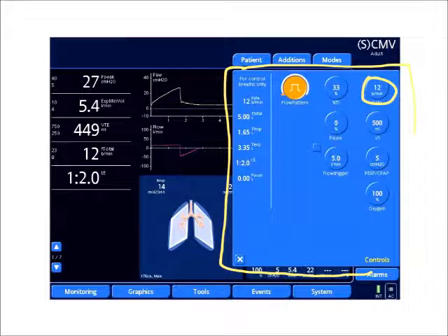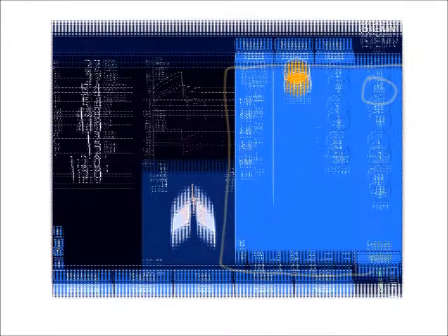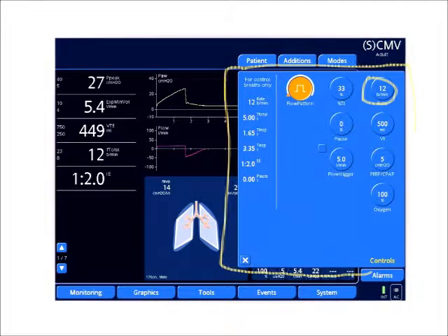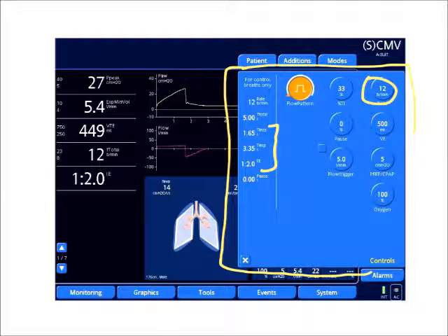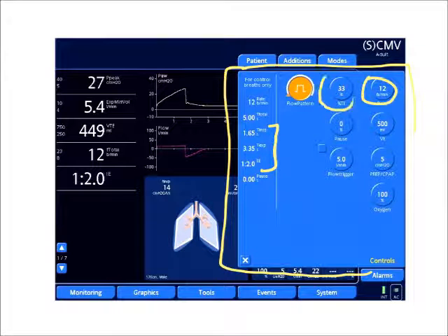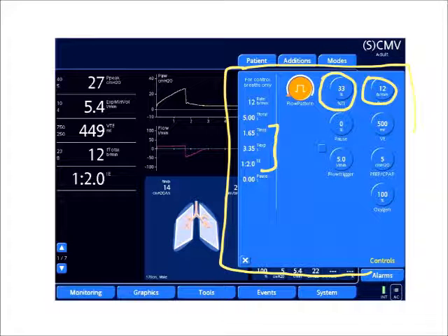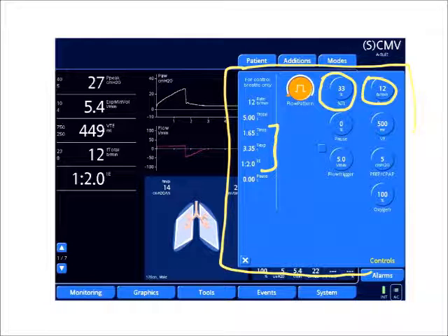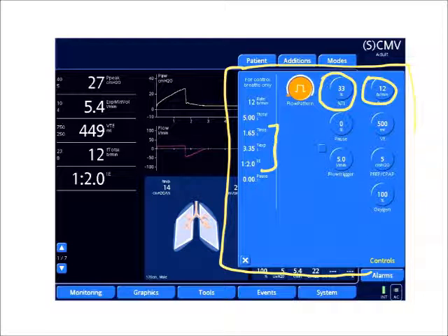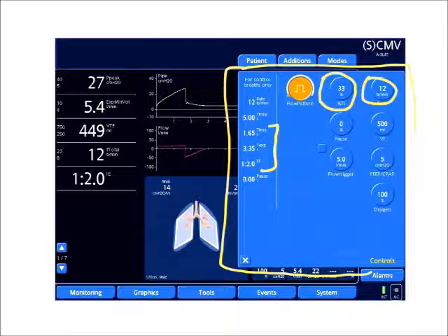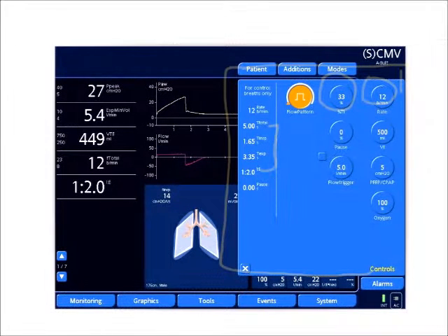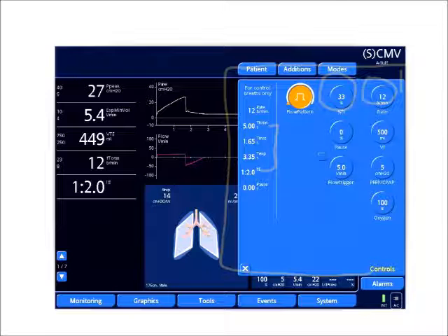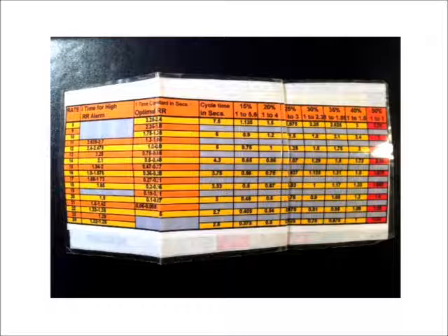As long as that's set, it's going to change these values over here. I have an inspiratory time, my expiratory time, my IE ratio, and that's all based on my frequency. My other operator set point is an inspiratory time percent of 33%. So when I change this frequency, it's going to change my inspiratory time, my expiratory time, and even my IE ratio. If you had a ventilator and you increased or decreased the respiratory rate or frequency, you'll see these changes act out over here in the smart window.